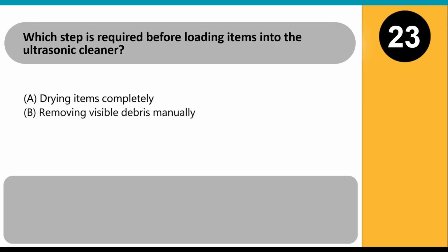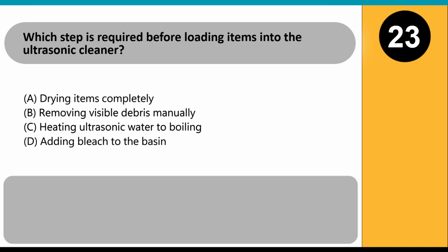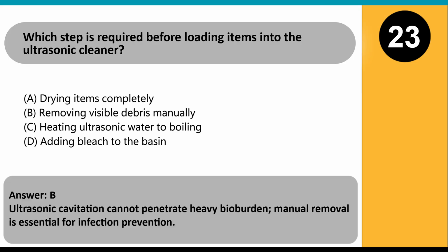Which step is required before loading items into the ultrasonic cleaner? A. Drying items completely. B. Removing visible debris manually. C. Heating ultrasonic water to boiling. D. Adding bleach to the basin. Answer B. Ultrasonic cavitation cannot penetrate heavy bioburden. Manual removal is essential for infection prevention.